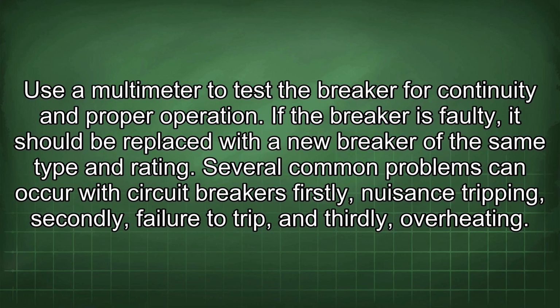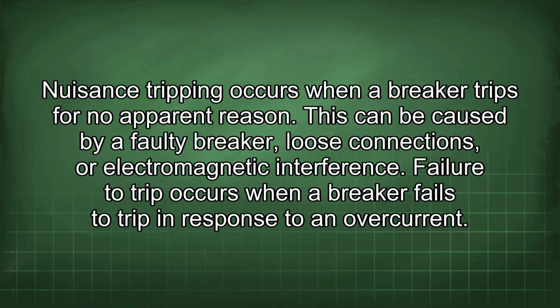Several common problems can occur with circuit breakers. Firstly, nuisance tripping. Secondly, failure to trip. And thirdly, overheating. Nuisance tripping occurs when a breaker trips for no apparent reason. This can be caused by a faulty breaker, loose connections, or electromagnetic interference.